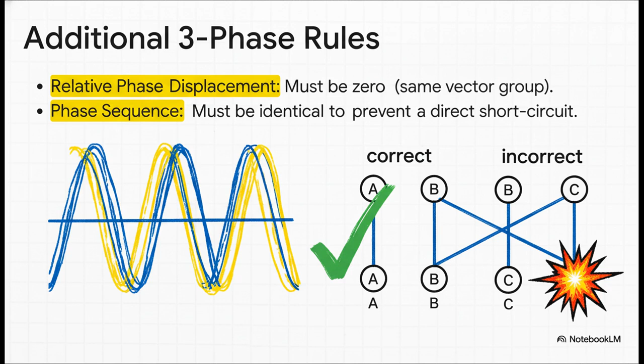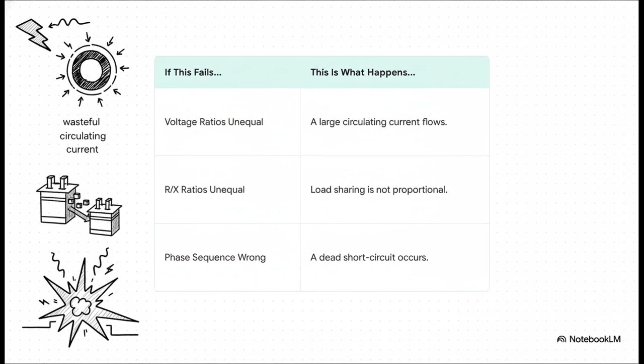If the R to X ratios are different, the transformers won't share the work fairly based on their size. You could have one transformer getting dangerously overloaded while the other one is just coasting along, barely breaking a sweat. And yeah, if you screw up the phase sequence on a 3-phase system, it's game over.